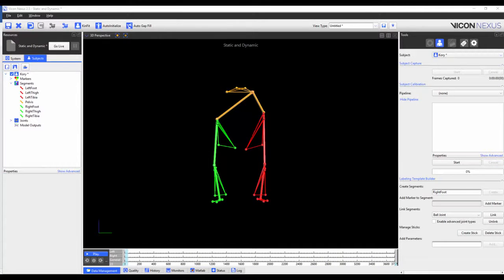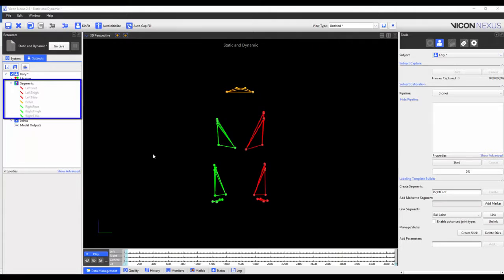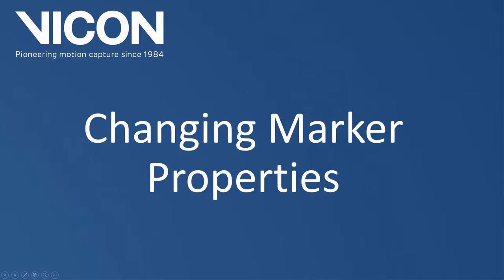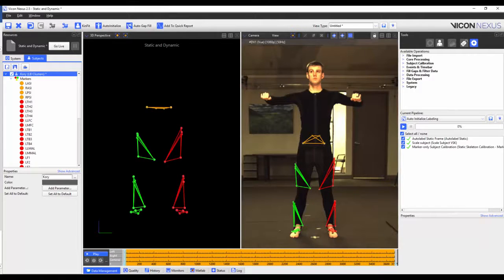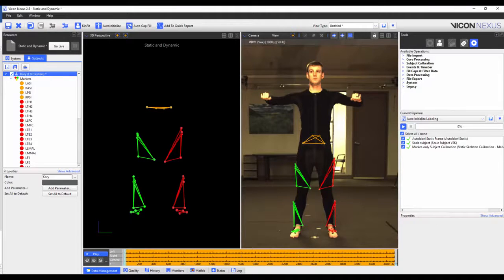It's worth noting that I build all the segments on the same frame. In this frame, all of the segments are calibrated, so I can link them. If I move to a different frame, the segments are no longer calibrated and I won't be able to link them. In the next part of this video, I'm going to show you how to change the marker properties. Nexus 2 is very flexible for these operations, and while I present them in a specific order, these changes can be done in parallel. You may want to rename markers before scrubbing through your ROM trial to make checking and relabelling markers easier. Please remember to create your segments and link them on the same frame.